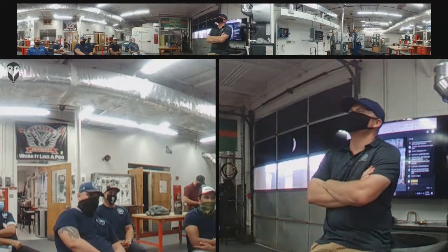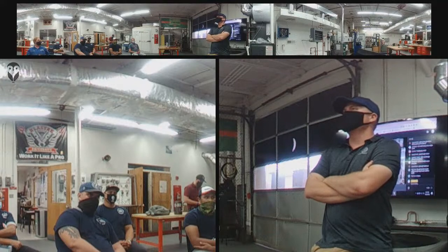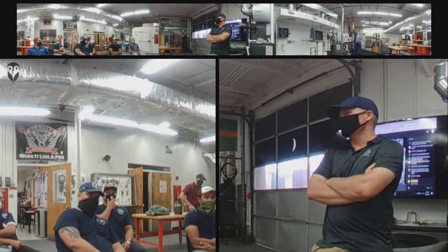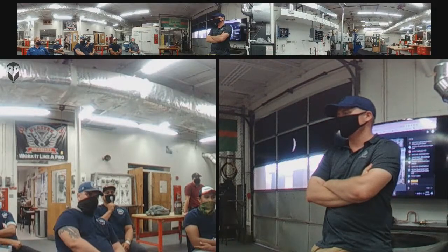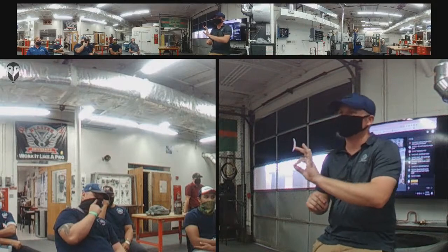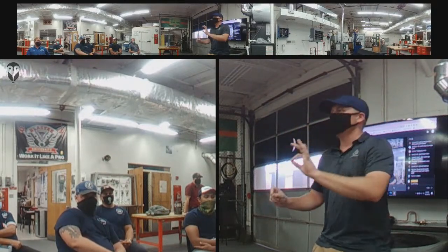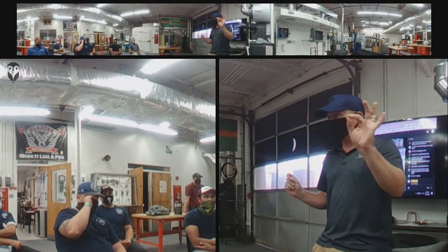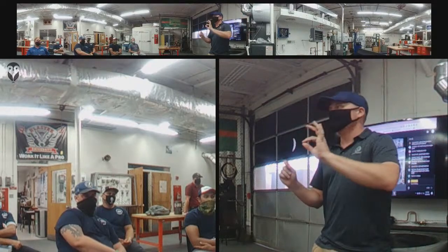Okay, all right. So we're maybe going a little too far here, but that's one where, if we can find a wiring diagram for that unit, it would be good to look it over and see exactly what you were seeing. Because if you're walking through a circuit, especially on the low voltage side, once you get past the coil on that relay, once you get on the common side of the circuit, you will stop seeing voltage.